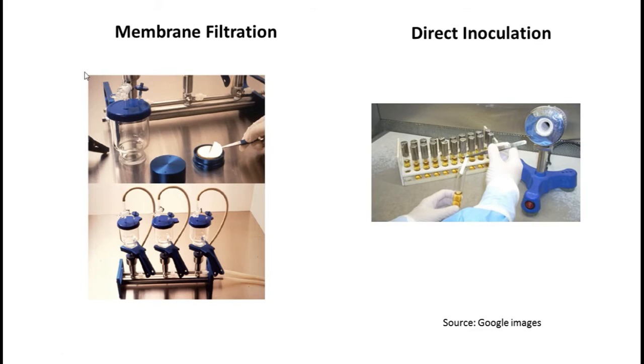To perform this test procedure, first of all, the entire unit is assembled and sterilized with the membrane in place. But that is for aqueous products. If oils are involved, then the membrane is required to be sterilized separately, and after thorough drying it can be assembled aseptically.